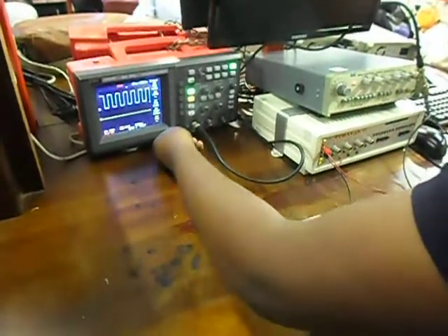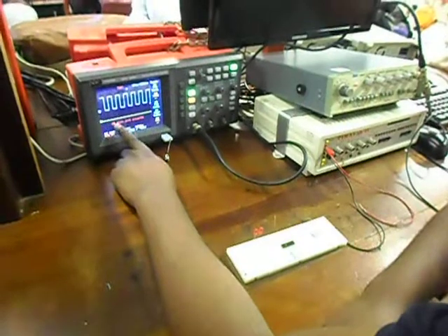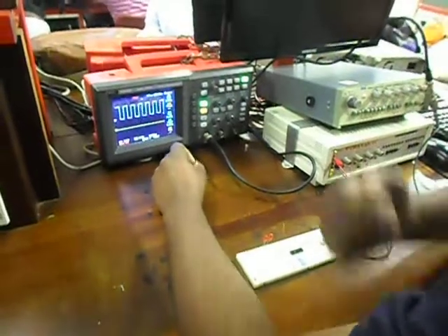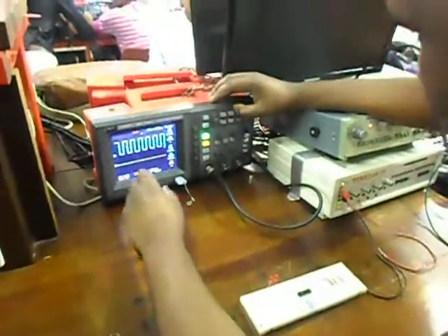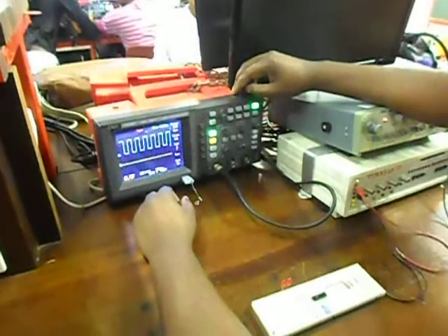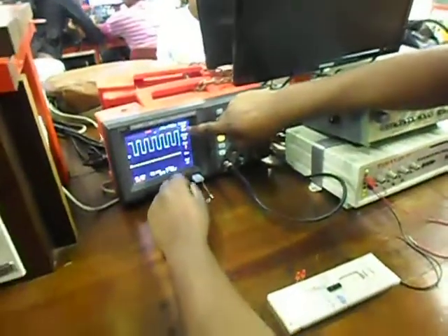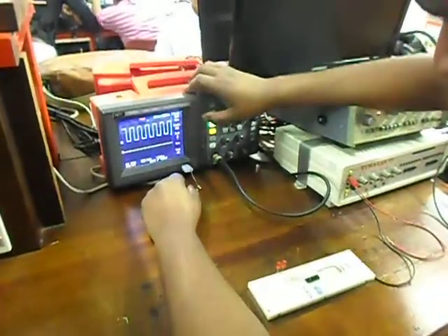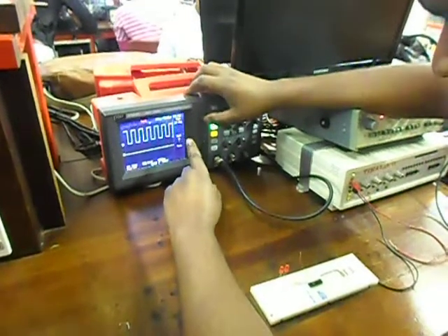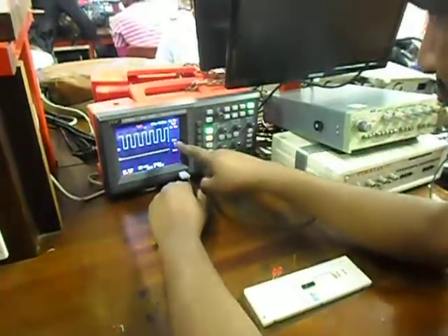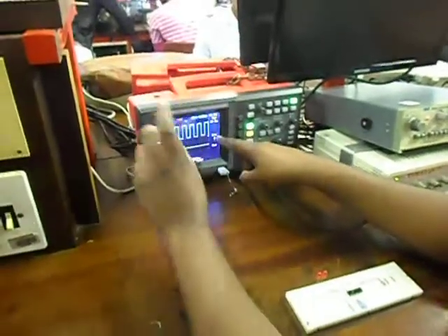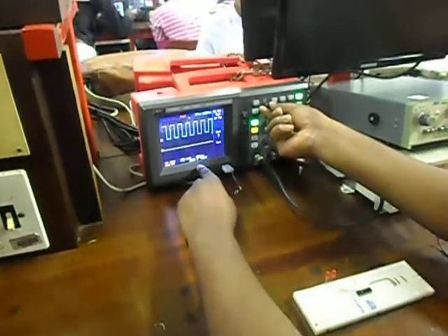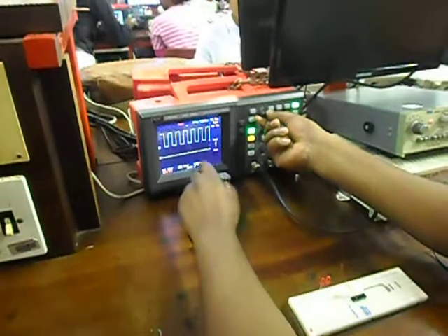So insert the USB. Device installed successful, so which means the USB is working. And then now you have to save the waveform. You go to storage and then the type of storage that you want. It's supposed to be bitmap, not waveform, not wave, not setup. So you keep on changing here until you see bitmap, and then this destination is going to be our picture number 1. So if you want this picture to be picture number 2, you adjust this one. So the destination is going to be picture number 2.